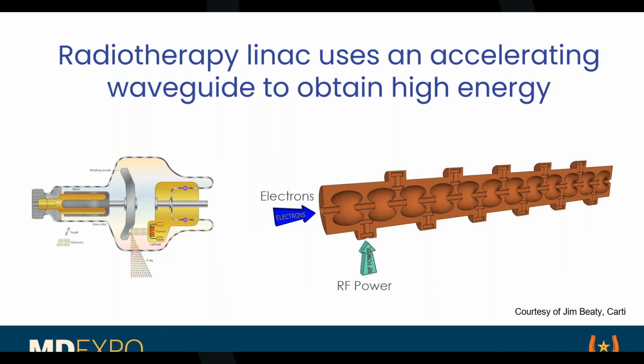We make the waveguides out of copper. When it's all polished and shiny, it's beautiful to see. It looks almost white, not like traditional copper. The way the microwaves resonate is all timed, and you don't need any electronics. It all happens naturally through the normal oscillations of the microwaves. Then the electrons get accelerated, and all you need is enough RF power and the right number of electrons, and then we can get high energies and high doses. That's at a high level how they work. It's quite different from the tube, but in many ways it's much simpler. Once we've built it, the laws of physics take over and it works. So it's actually not that hard.